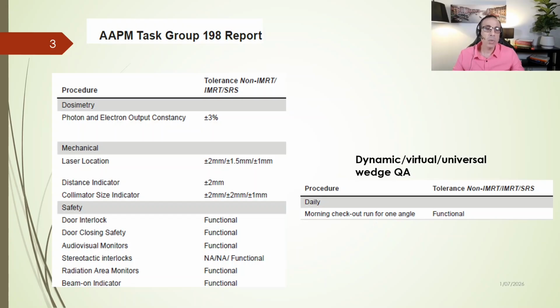Let's start with dosimetry. The most important parameter we assess each day is beam output constancy. Its tolerance is plus or minus 3% for both photon and electron beams. The second component is mechanical and imaging accuracy. The test verifies that the machine can deliver radiation precisely to the intended location.